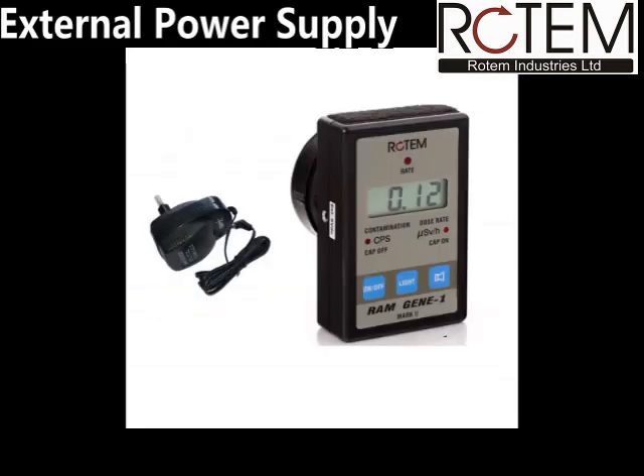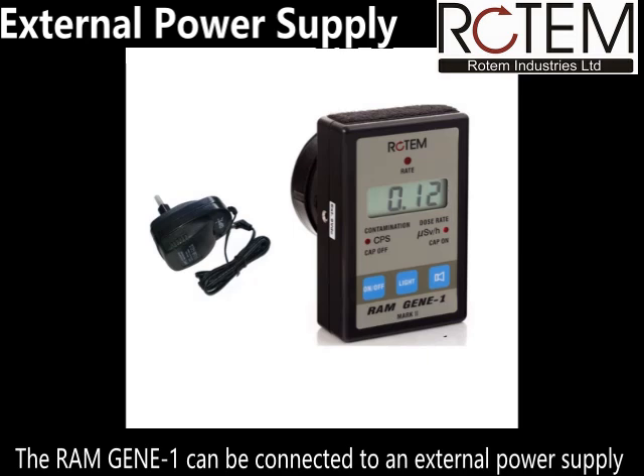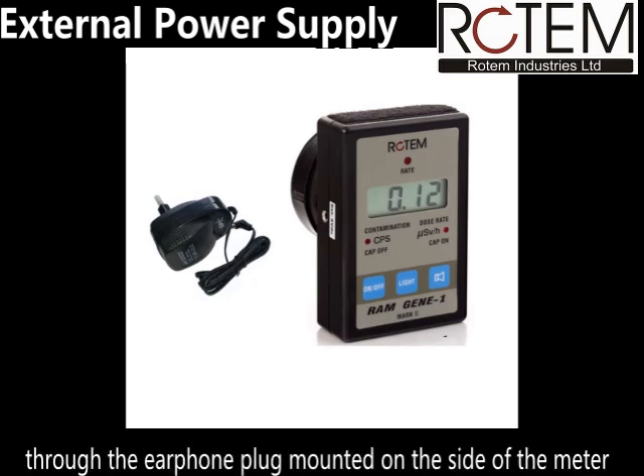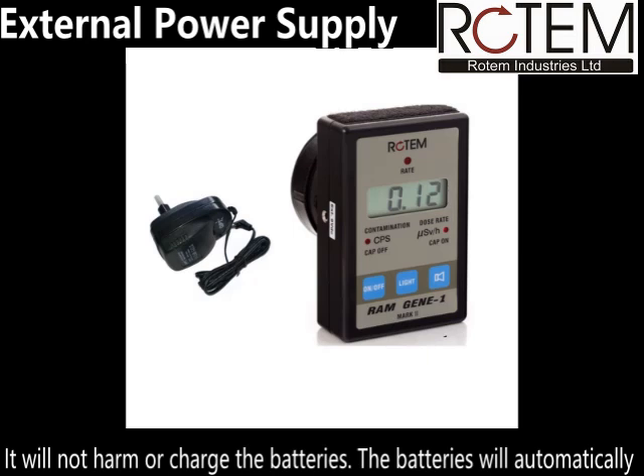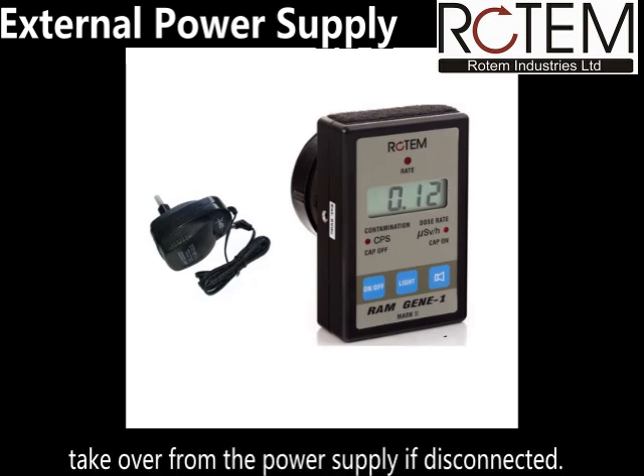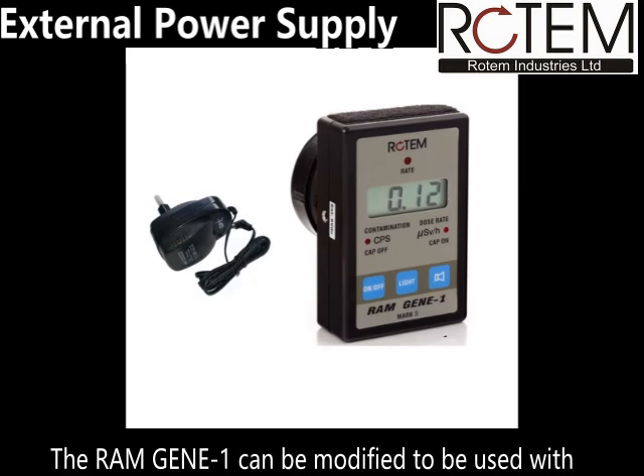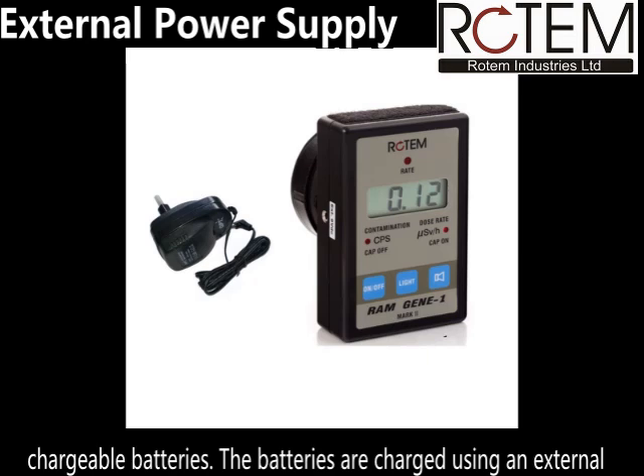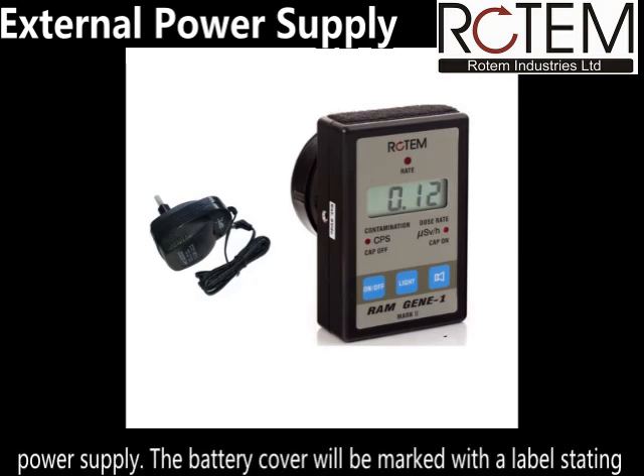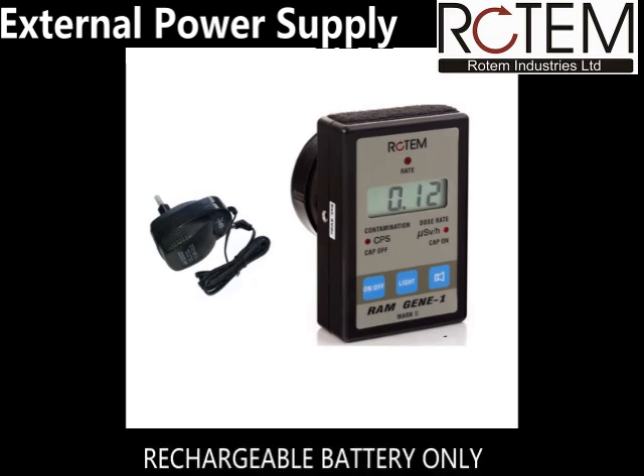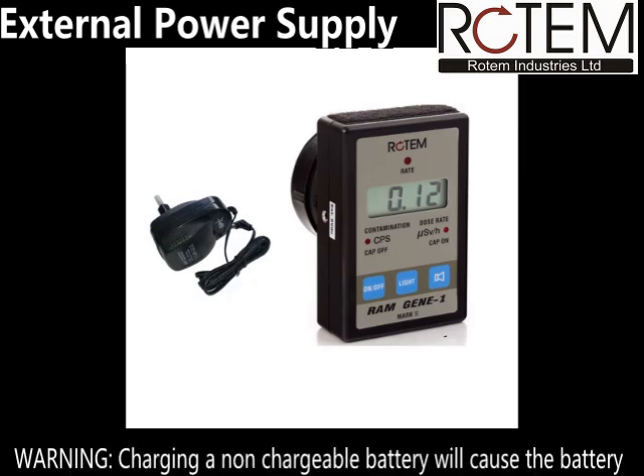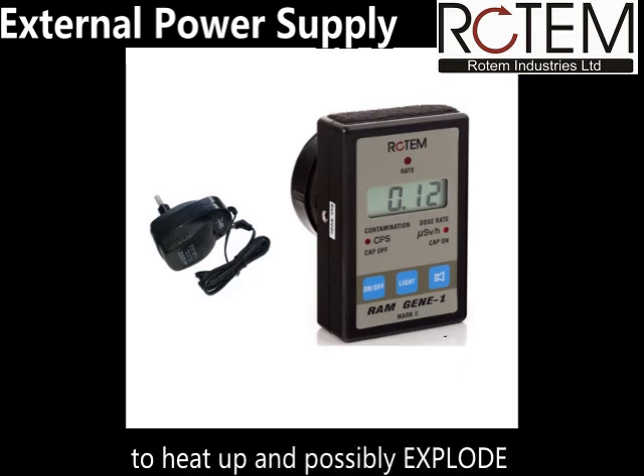The use of an external power supply. The RAM Gene 1 can be connected to an external power supply through the earphone plug mounted on the side of the meter, which will not harm or charge the batteries. The batteries will automatically take over from the power supply if disconnected. Using chargeable batteries. The RAM Gene 1 can be modified to be used with chargeable batteries. The batteries are charged using an external power supply. The battery cover will be marked with a label stating rechargeable battery only. Warning: charging a non-chargeable battery will cause the battery to heat up and possibly explode.